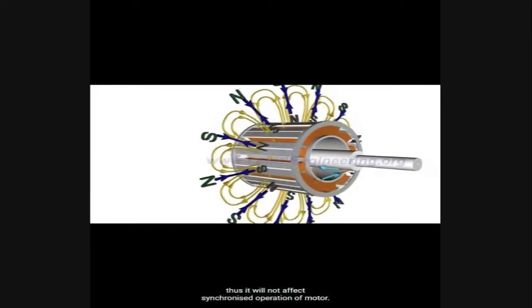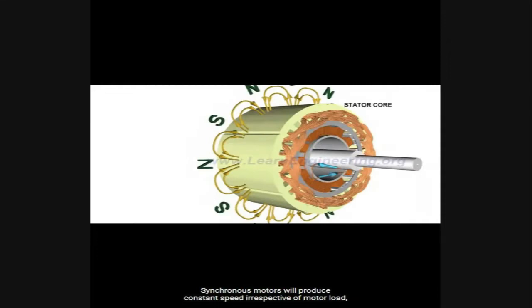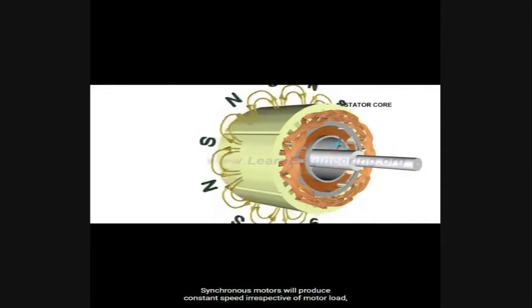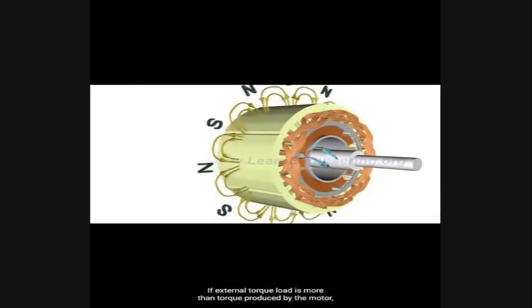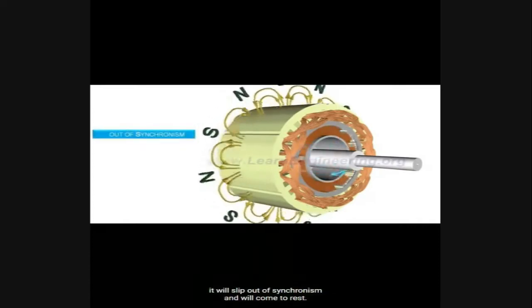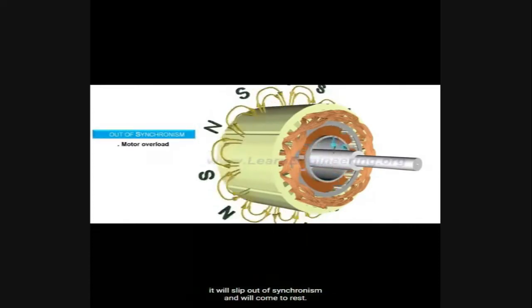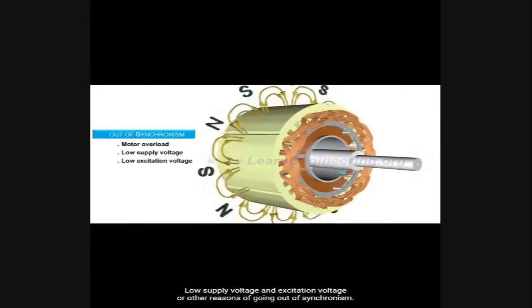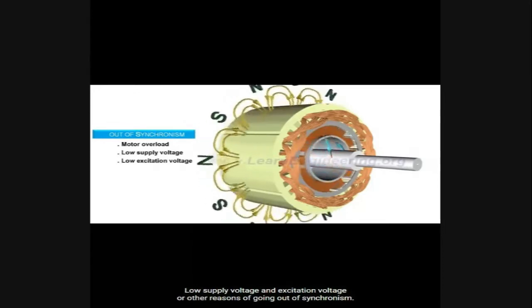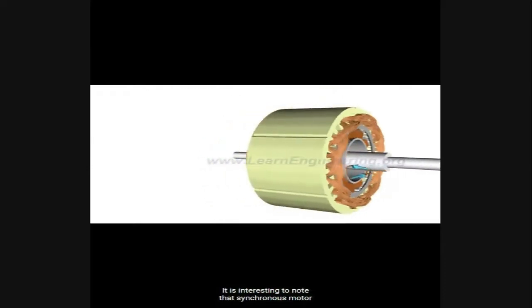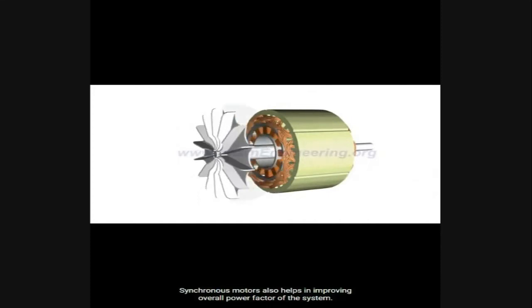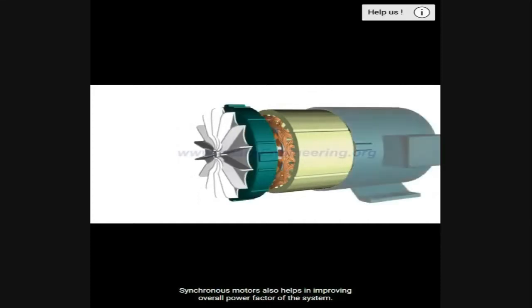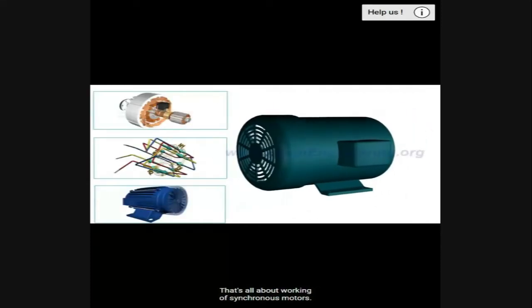Synchronous motors produce constant speed irrespective of motor load, as long as the load is within the motor's capability. If the external torque load exceeds the torque produced by the motor, it will slip out of synchronism and come to rest. Low supply voltage and excitation voltage are other reasons for going out of synchronism. Notably, a synchronous motor has the same constructional features as an alternator, and it also helps in improving the overall power factor of the system.